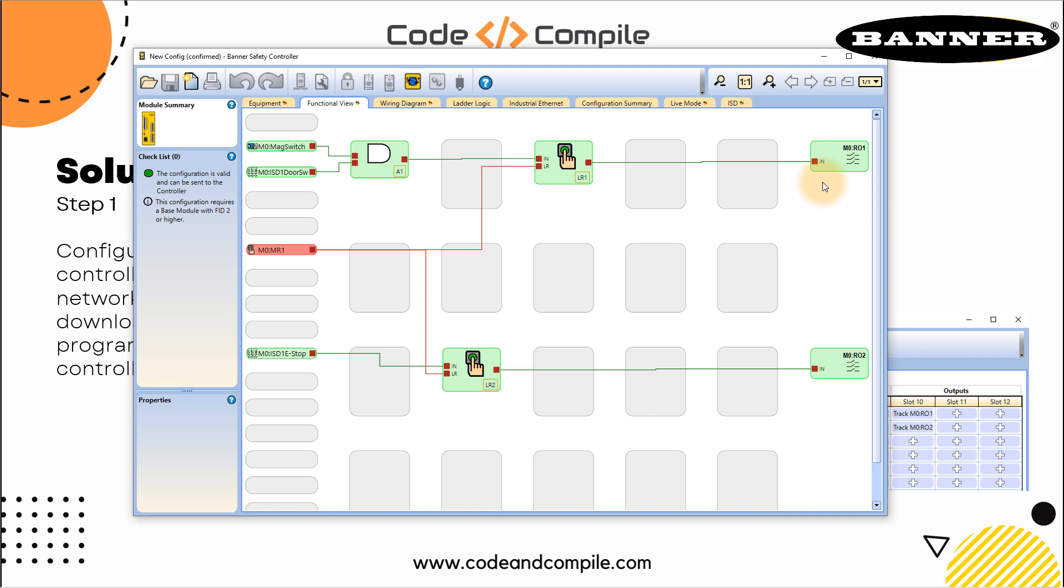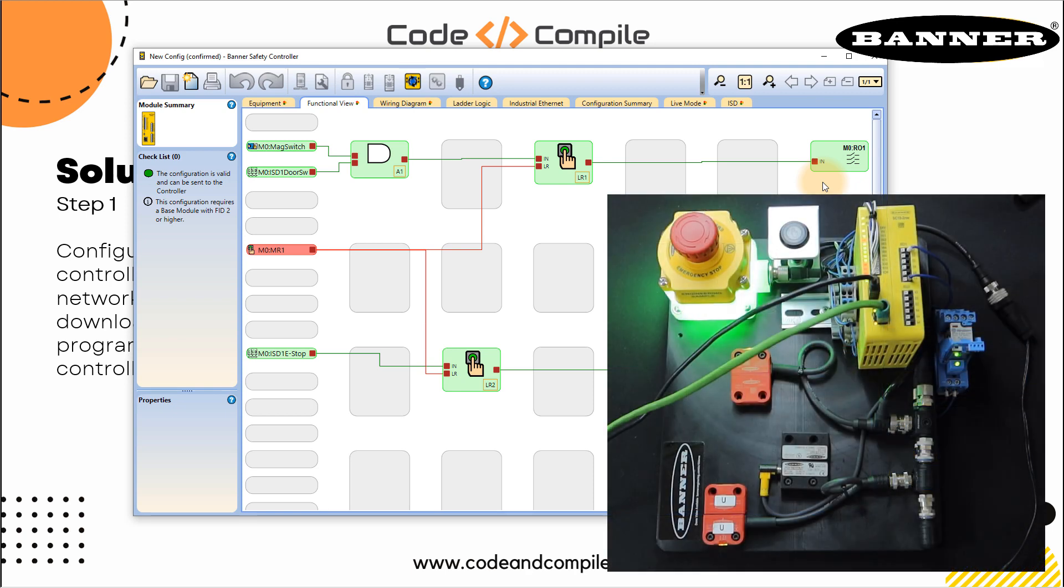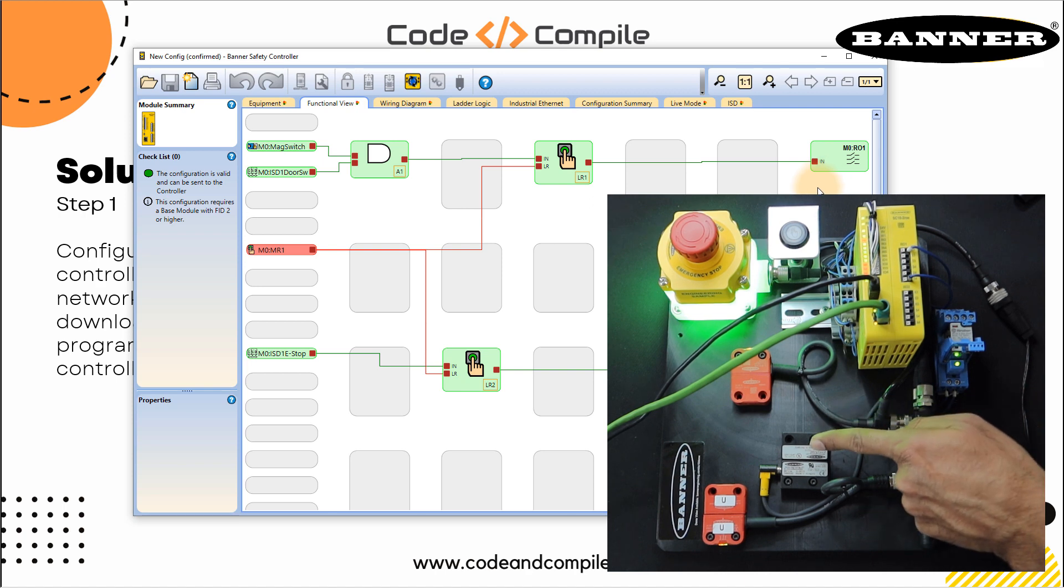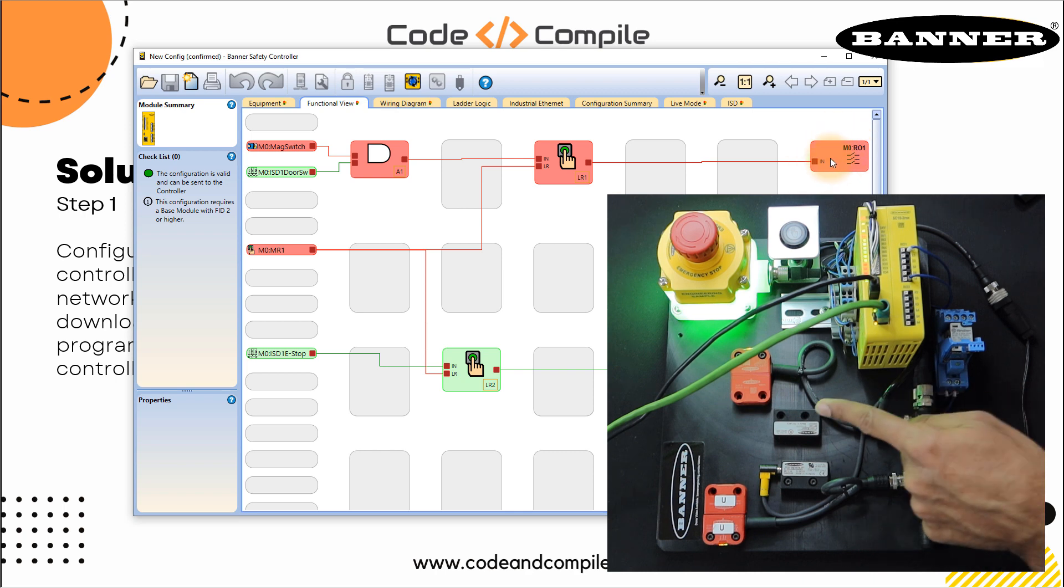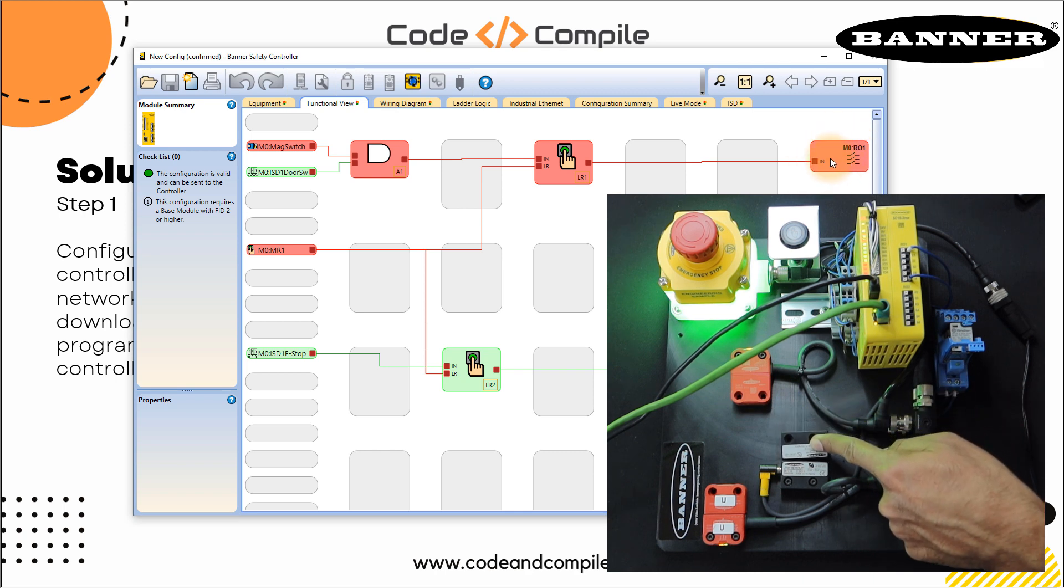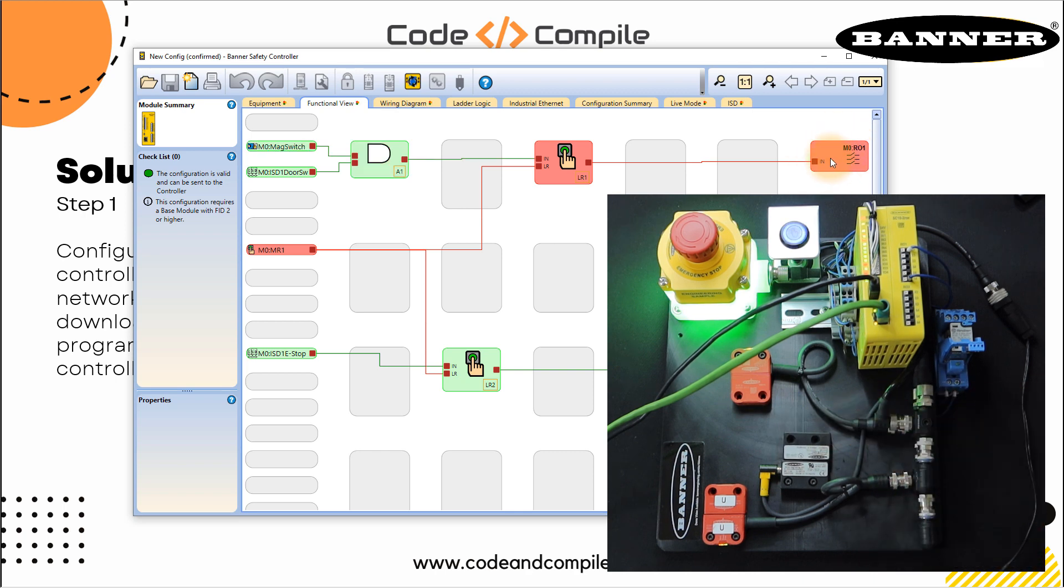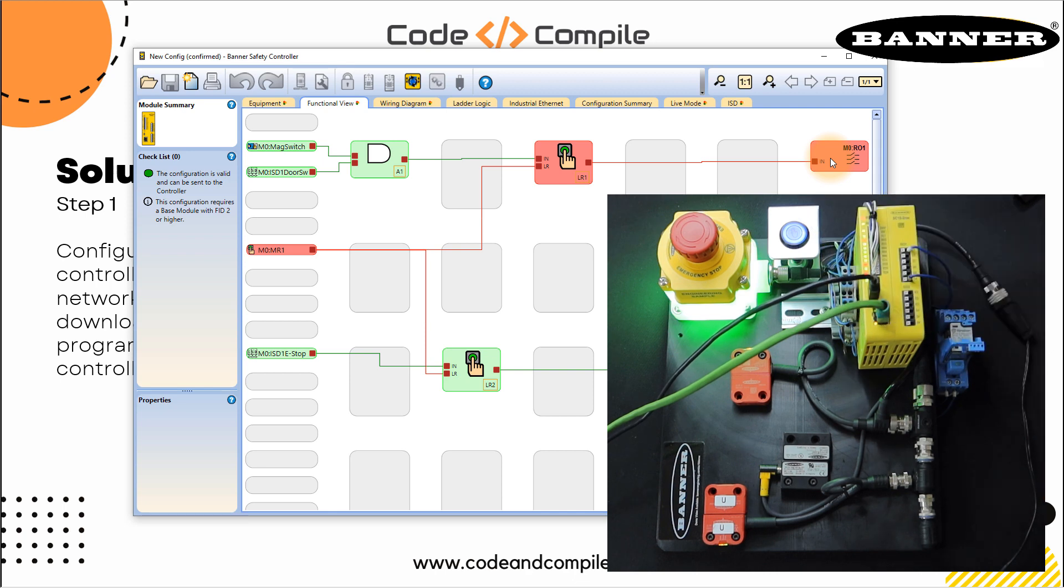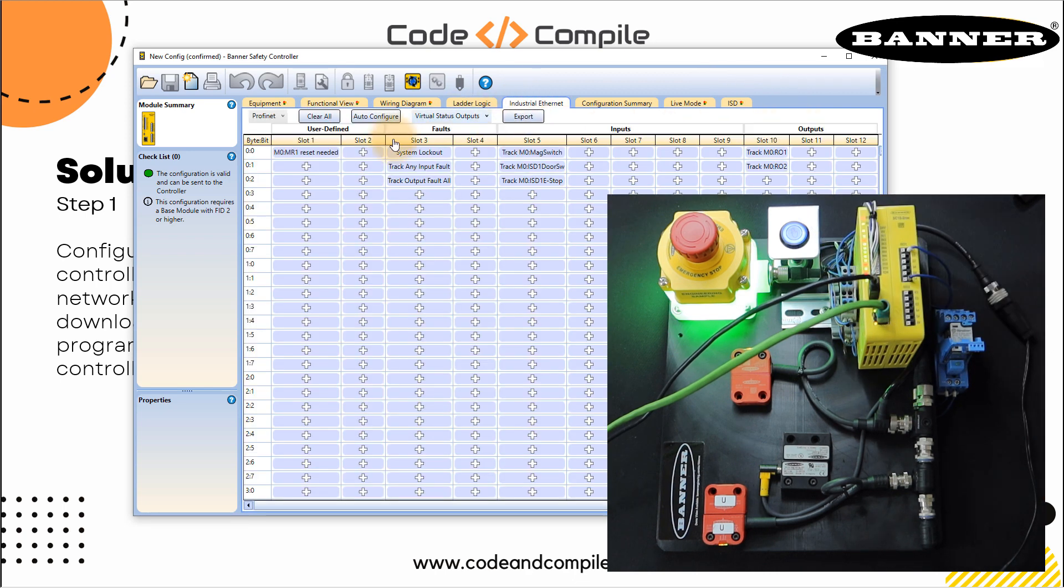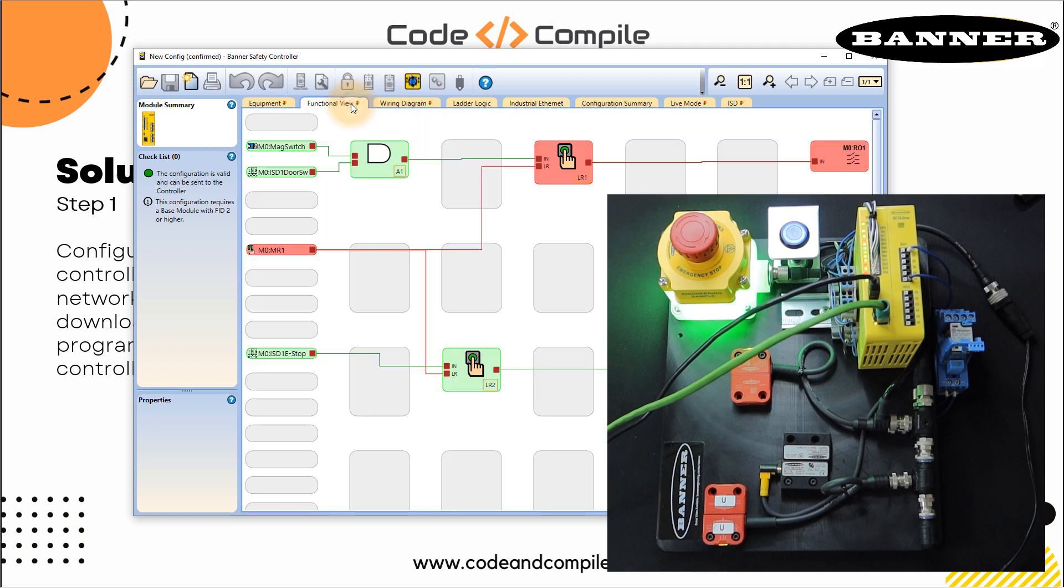I'm going to start my controller and then I'm going to break the circuit. You can see my hardware kit on the camera, and I'm going to break the circuit. Now the circuit is broken, one of the outputs is false. So now if I bring back the circuit, I have an indication which means reset is required. This is the status which we can send via industrial Ethernet and via PROFINET to the PLC. This is the function when your reset is required in your circuit.